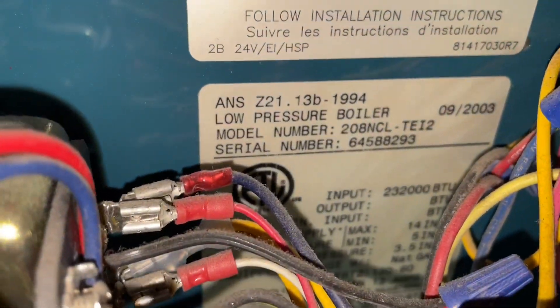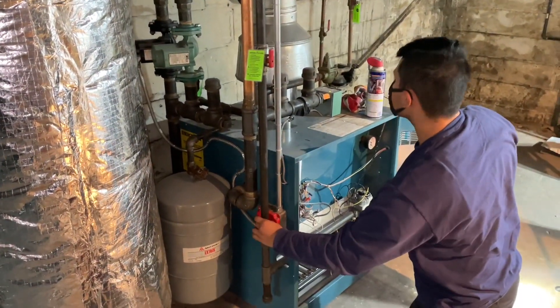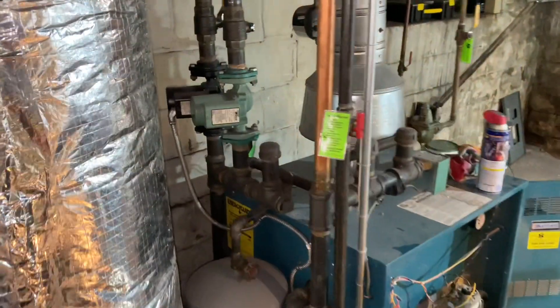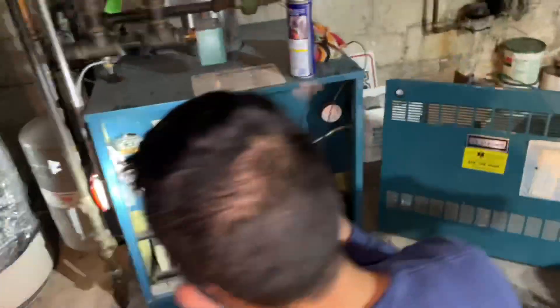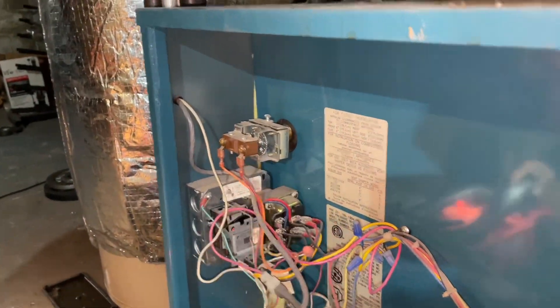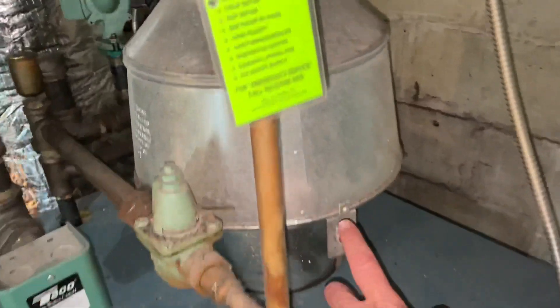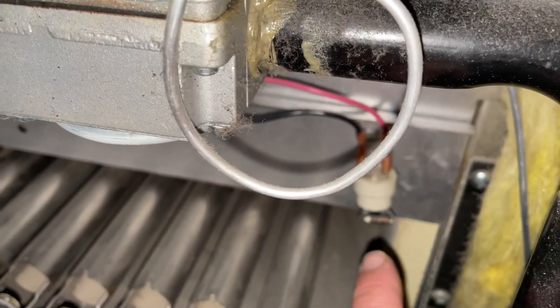232,000 gross/net BTUs — we're going to do our seasonal tune-up on this boiler. First thing I like to do is just be observant of my surroundings, make sure we don't have any rust or corrosion anywhere, nothing's leaking. You have the Extrol number 60 right there, take a look at the pressure. Fan center relay, high limit aquastat, there's our gas valve, this is our blocked vent switch, spill switch, automatic vent damper, and down in this corner that's our ceramic thermo disc — that's the rollout switch. We service this thing every year and as you can see it is clean, so this should be pretty routine.